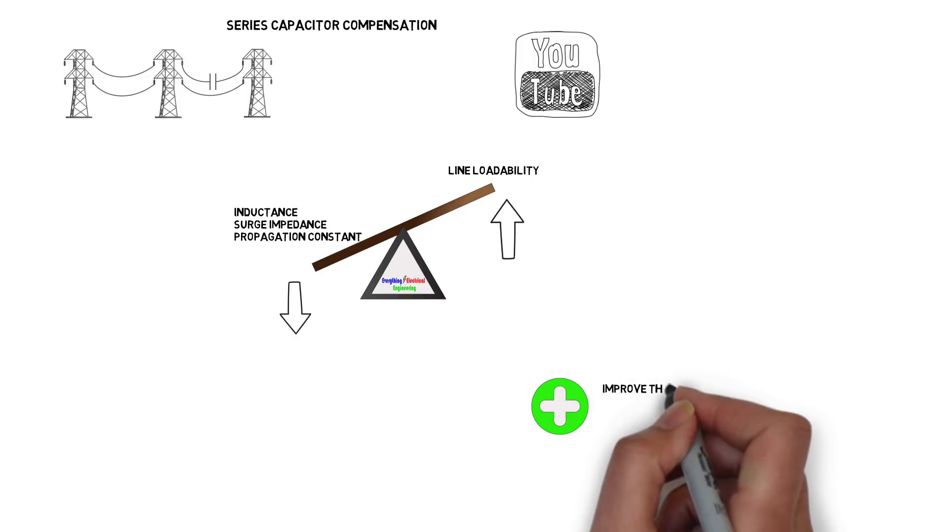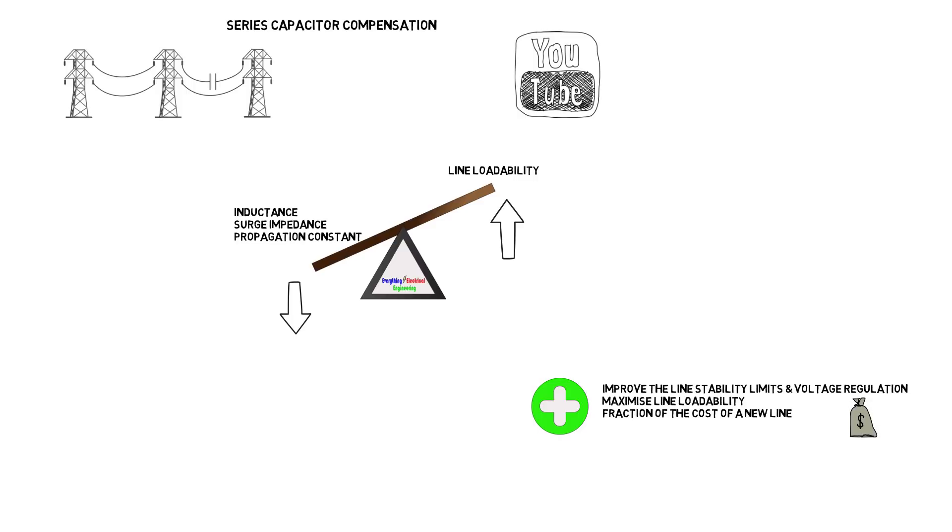Series capacitor compensation will improve the line stability limits, voltage regulation and maximize the line loadability for a fraction of the cost of a new transmission line. However, there are some drawbacks to this configuration, such as having the full current going through the capacitor will cause harmful overvoltages during certain fault conditions. Special protection switchgear to automatically detect and bypass high currents during fault conditions is required. There are other issues with harmonics and low frequency oscillations, which need to be taken into consideration, as this may negatively affect turbine generators and mechanical systems.